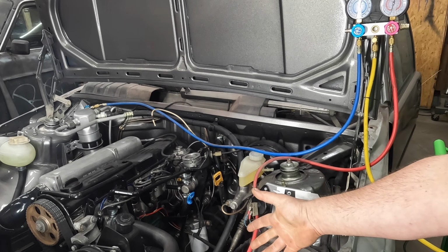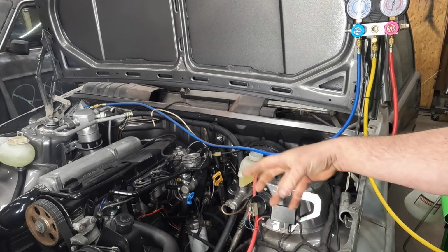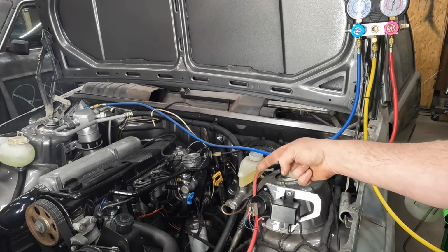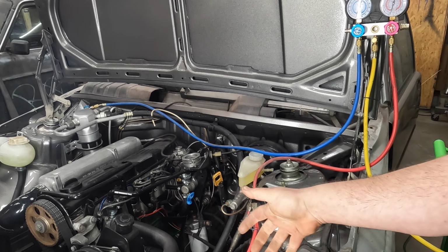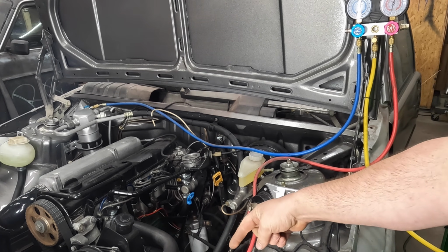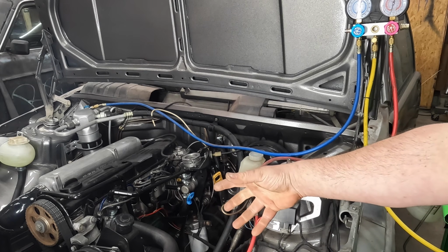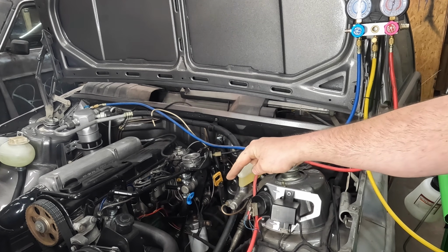That does not compress. So normally, to charge an empty system, you would first start it and then start shoving refrigerant into it and let the compressor kick on when it feels like it. But since I know that's just going to start running as soon as I turn on the AC, I want to put some in there beforehand.